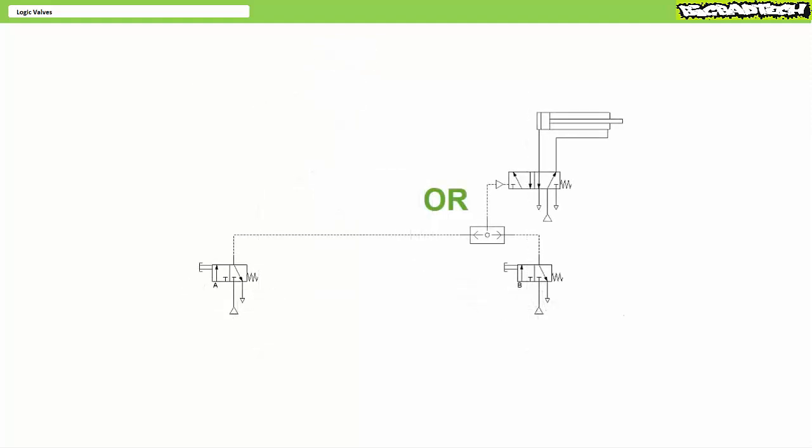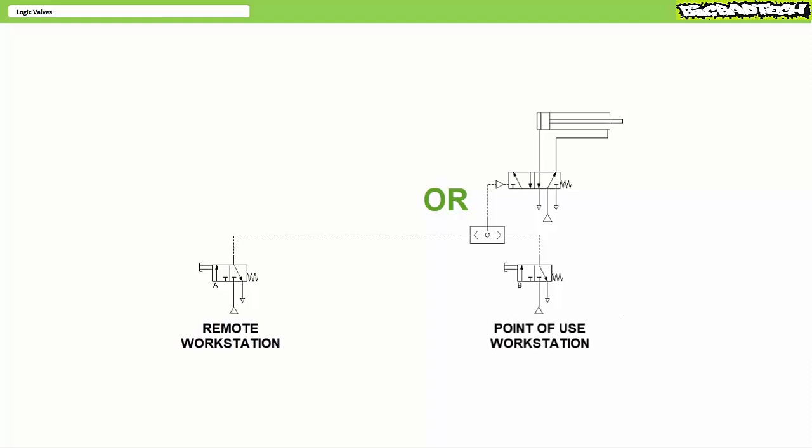OR valves, in contrast, are commonly used in pneumatic circuits which necessitate operation from more than one location. The classic example is an operator stationed some distance away and another station at the point of use. An operator sitting at a desk some distance away can extend and retract the cylinder using push button A. Similarly, a technician servicing the equipment, wishing to test it out, can extend and retract the cylinder using push button B at the point of use.